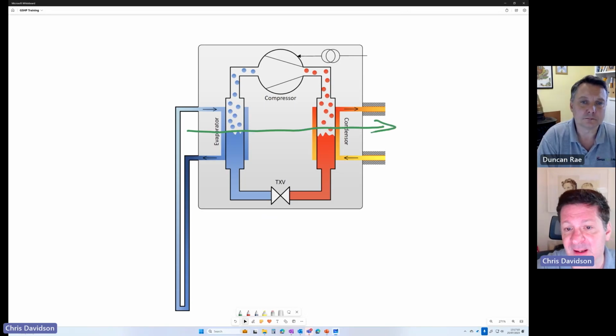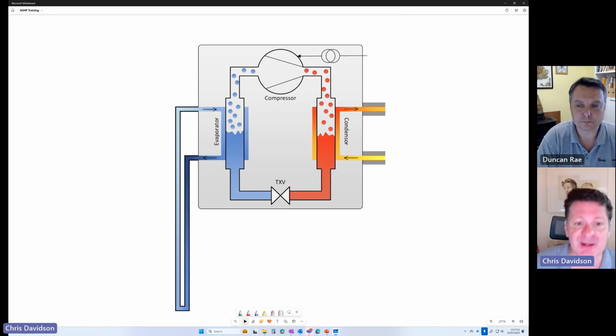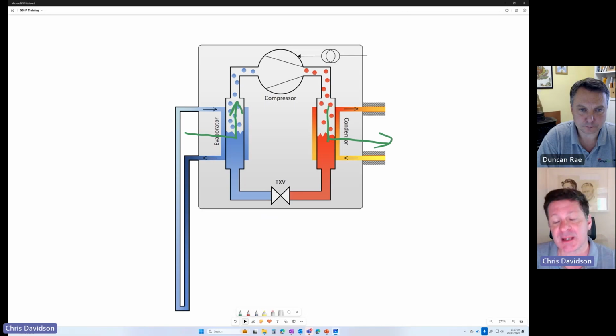So it just moves heat like that. How it actually does it is it manipulates the pressure in a liquid gas circuit to allow that liquid to evaporate, turn to a gas, and therefore pick up heat at a low temperature, and then condense, and therefore drop that heat at a higher temperature. It manipulates the pressure in that liquid gas circuit by using a compressor, which consumes electrical energy.